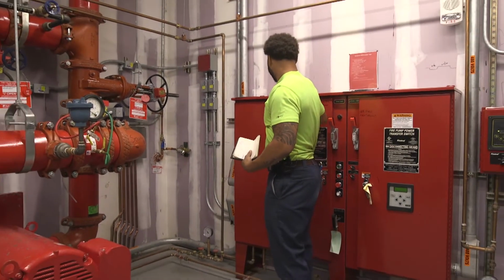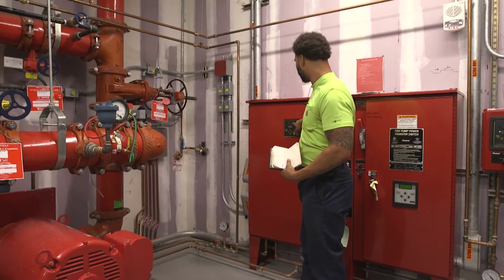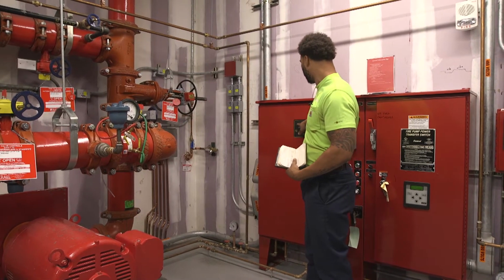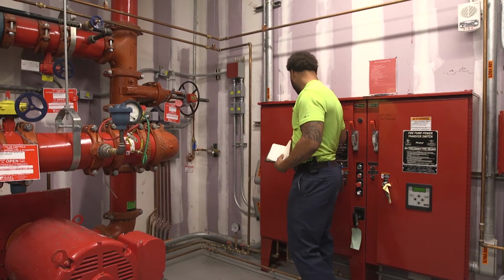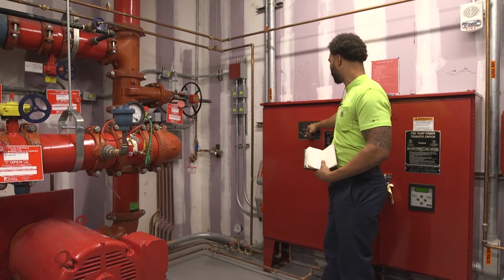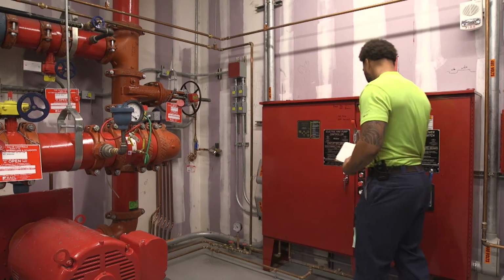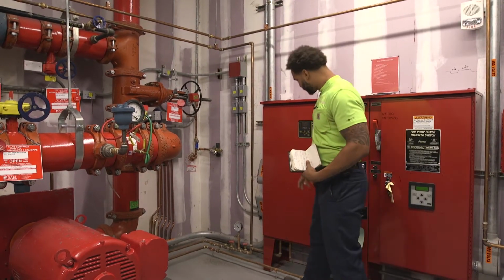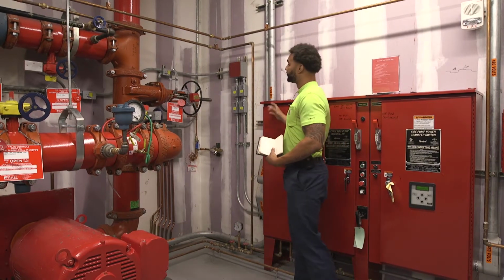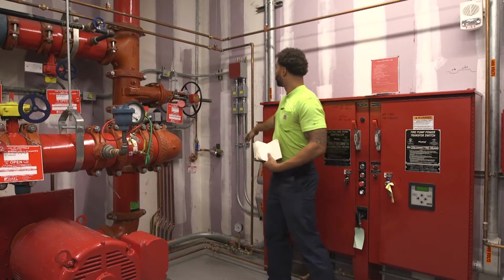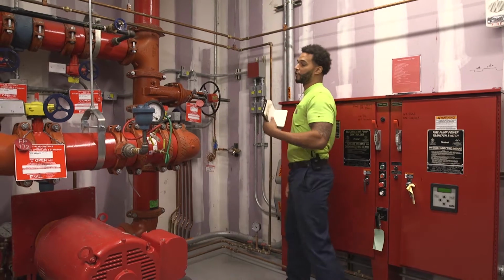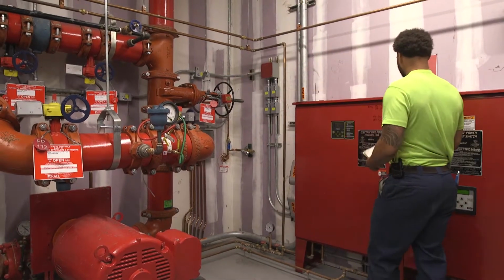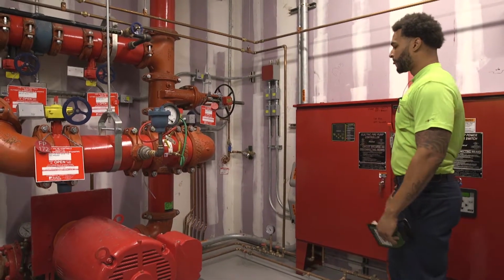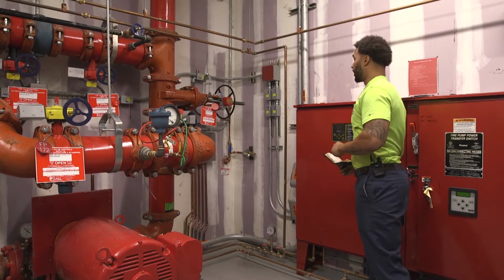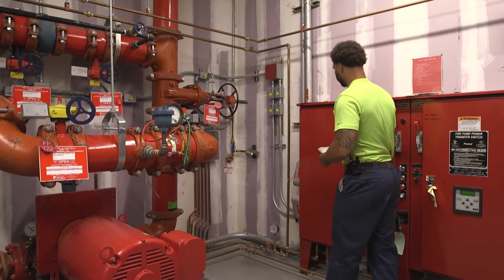Here's our input screen. Here we have our system pressure, and we have our regular voltage. Like I said, we have about 485, 486 going through our 3 phases here. Coming out of our controllers here are our sensing line. Our sensing line is basically what reads pressure from our fire pump system and our actual controller. And I'll go to that sensing line shortly throughout the installation.